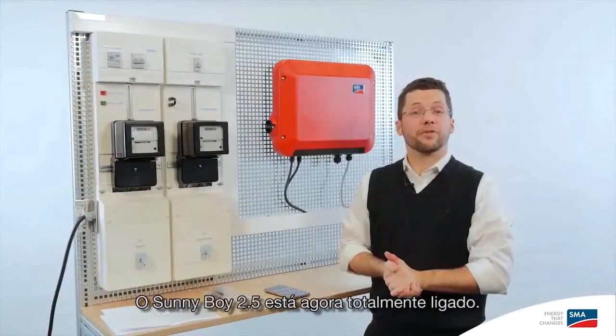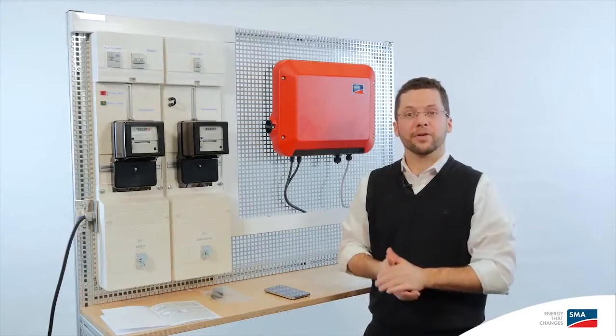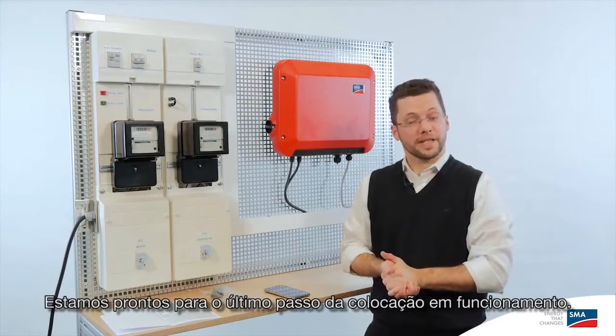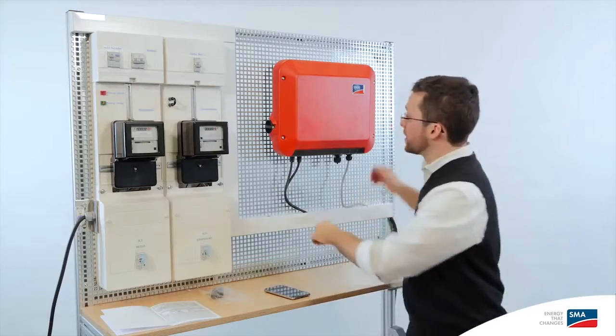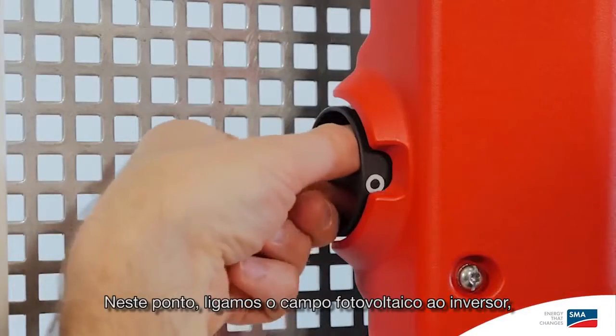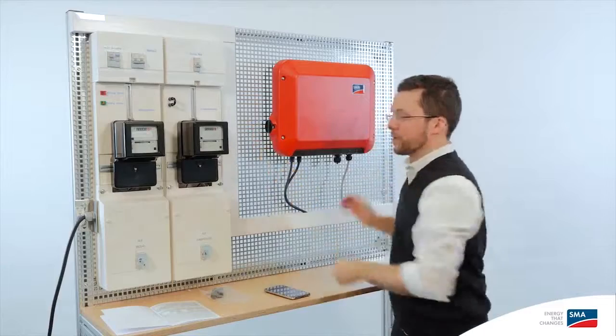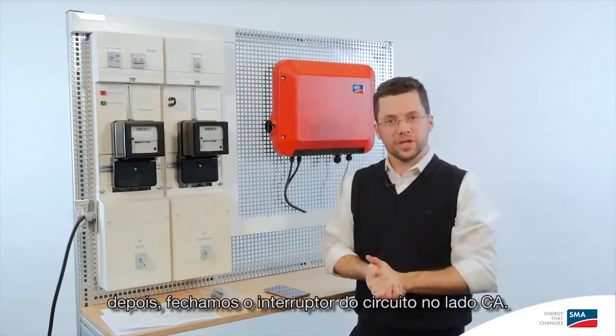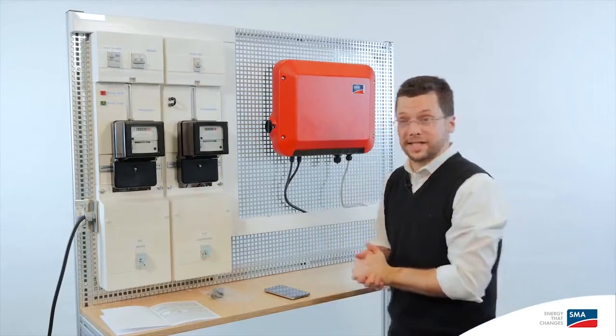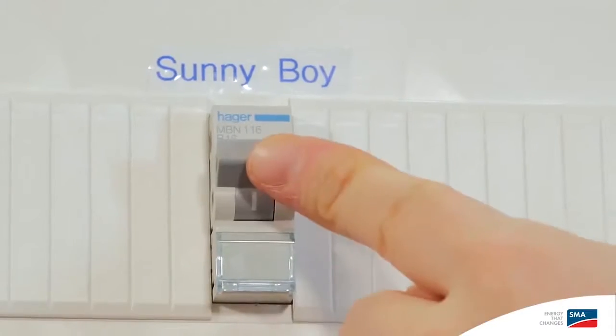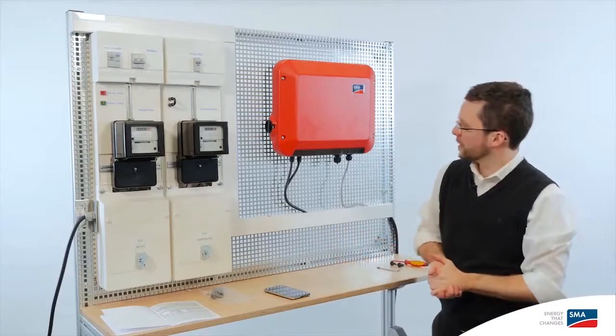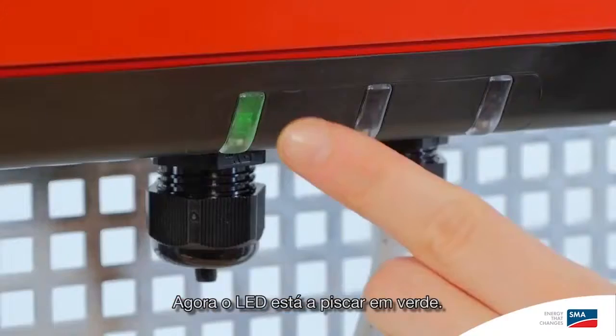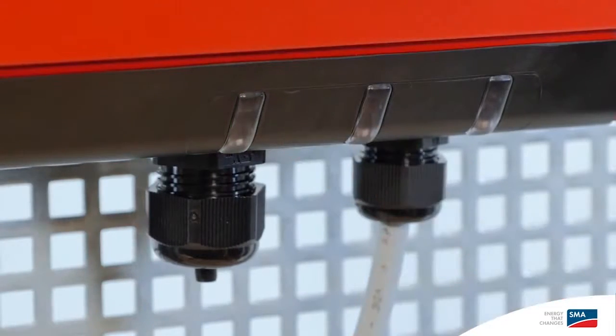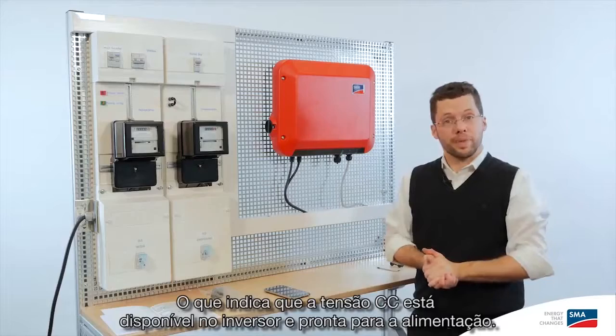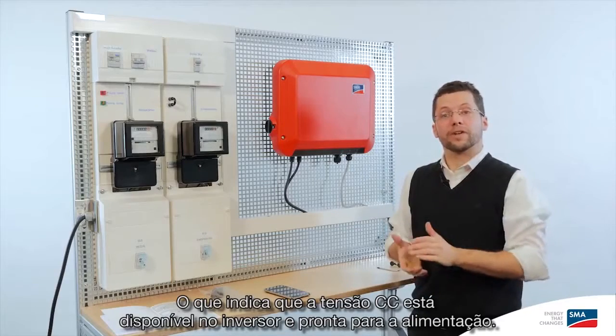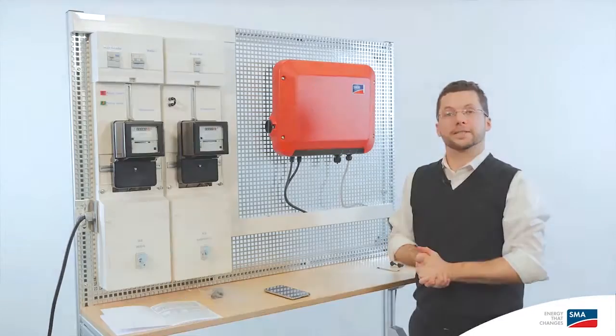The Sunny Boy 2.5 is now fully wired. We're ready to go on to the final step of commissioning. On that note, we hook up the power to the PV array, and next we also close the circuit breaker on the AC side. Now the LED is blinking green, which tells us that DC voltage is available and the inverter is ready for feed-in.